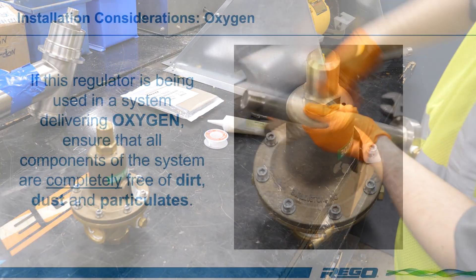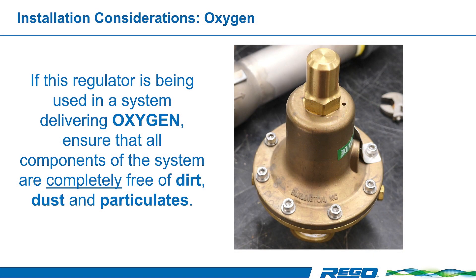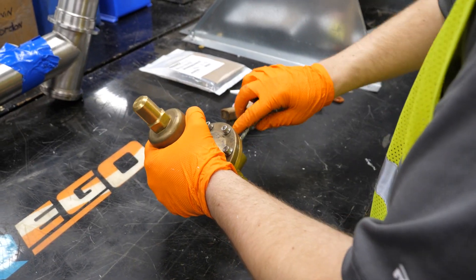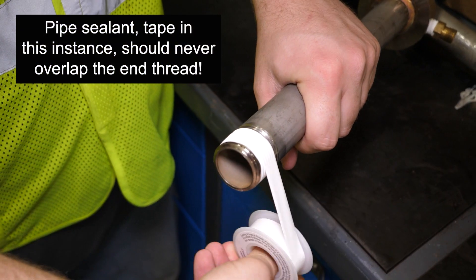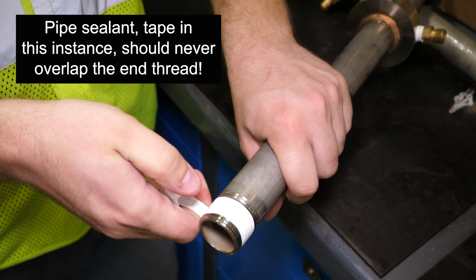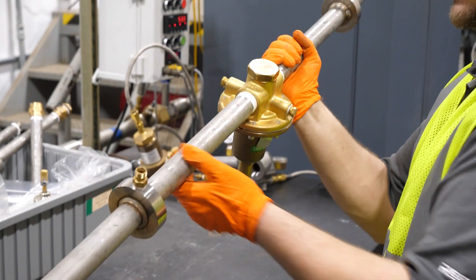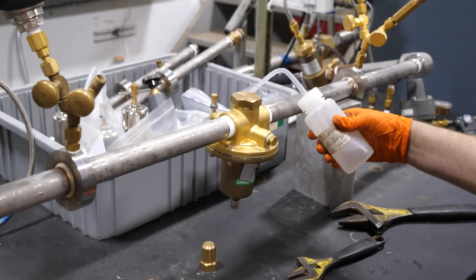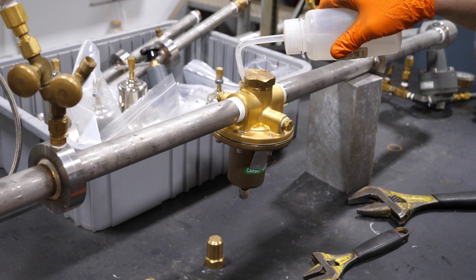If the regulator is used for oxygen, you must ensure that all components of the system are completely free of dirt, dust, and particulates. Apply a pipe joint compound suitable for the gas service, such as PTFE or Teflon tape, to the male threads on the piping. Install the regulator according to the flow direction, noting the inlet and outlet stamped on the regulator. Follow all local and national codes and standards for pressure testing and leak testing during the installation.